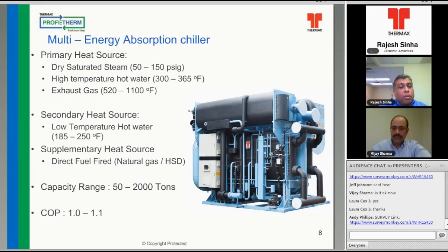Generator and condenser are separated out, and this is available from between 0.25 to 40 megawatt of heating capacity, and sees a heating COP of 1.65 to 1.75, which is the industry highest. The temperature range of the hot water which is thereby generated is about 95 to 195 degrees Fahrenheit, and this can offer a delta T which is as high as 100 degrees Fahrenheit. This is an absolutely new product which has been launched about 1.5 years back, and just available in the U.S. from this year onwards, from January.